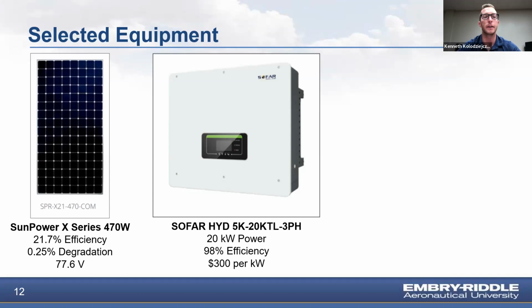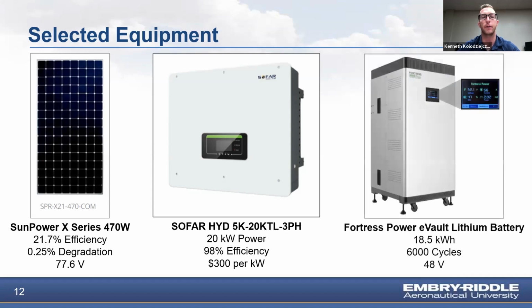The selected battery is the Fortress Power eVault lithium battery. Lithium batteries were decided over lead acid batteries due to their high cycle life and depth of discharge. The Fortress battery has a life of 6,000 cycles and depth of discharge of 80%. Safety was an important factor in our equipment selection due to the buildings being highly populated. The selected battery is a lithium iron phosphate battery, which is the safest type of lithium battery.